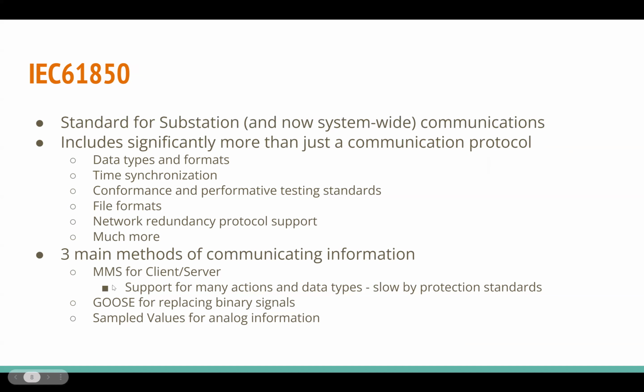Originally, the term 61850 was described as a substation communications standard. Over time, they realized it's used even outside of substations, so they changed the naming scheme to say 'system' instead of 'substation'. For example, configuration files used to be called Substation Configuration Language; now it's called System Configuration Language.